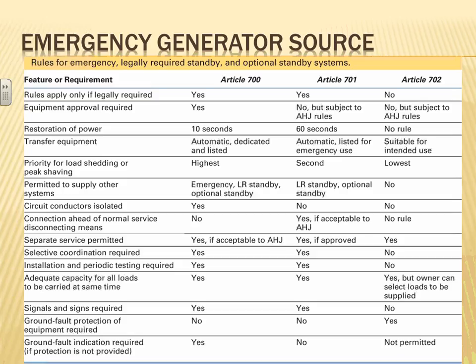That's your emergency for people. And then above that becomes what's legally required standby system. What comes to my mind is fire alarm, fire pumps, jails. Certain systems in jails will qualify as legally required standby system, where the government decided that this system is so important for security, whatever, that it needs to be backed up by power. So that's your legally required standby system versus emergency system.